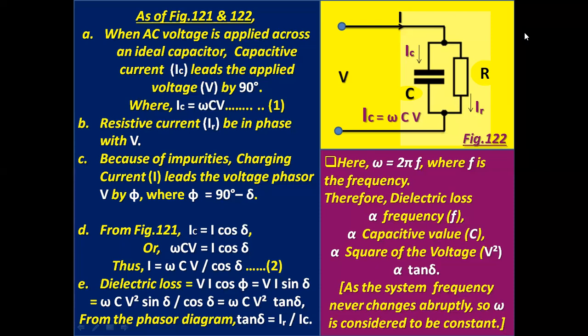As per the phasor diagram, tan delta equals IR by IC. Here, omega equals 2 pi f, where f is the frequency. Therefore, dielectric loss is directly proportional to frequency, directly proportional to capacitive value C, directly proportional to square of the voltage, and directly proportional to tan delta. As the system frequency never changes abruptly, omega is considered to be constant.